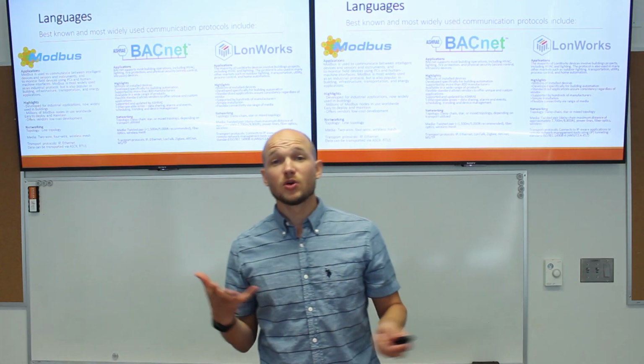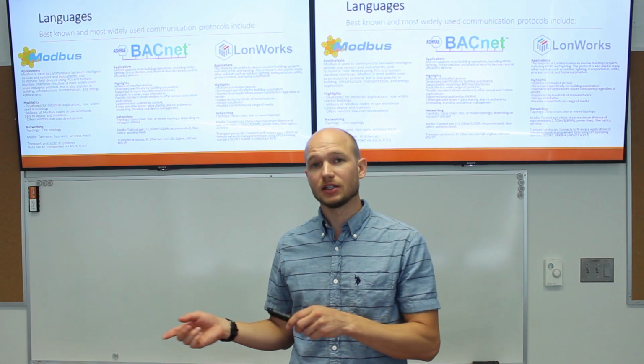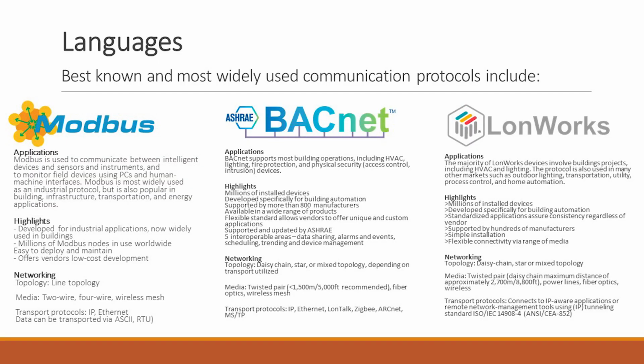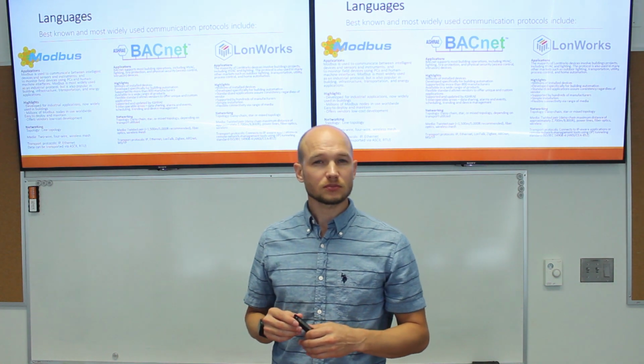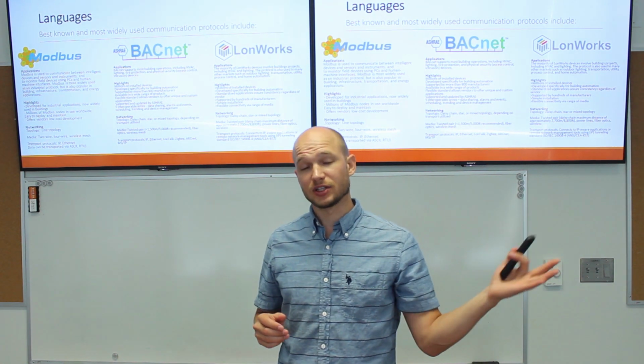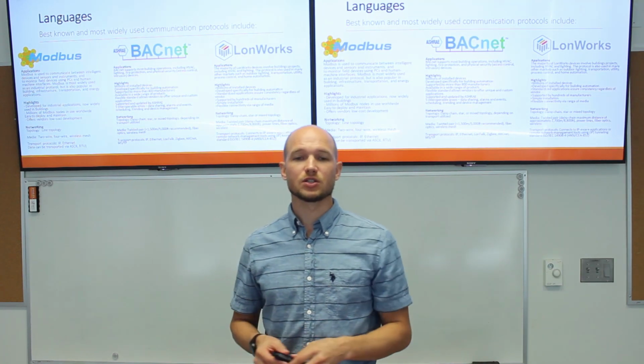So like I said, the three most popular languages that you're going to hear: Modbus, BACnet, LONWORKS. Modbus is, I think, the oldest. It was originally started for industrial applications. Still used pretty widely, but in building automation systems, you're going to see it mostly for energy applications, such as electric usage in your facility, or natural gas, a pulse meter. Some of that stuff will communicate through Modbus to a JACE controller.